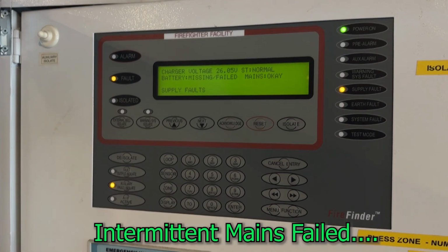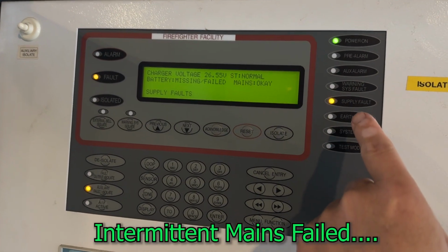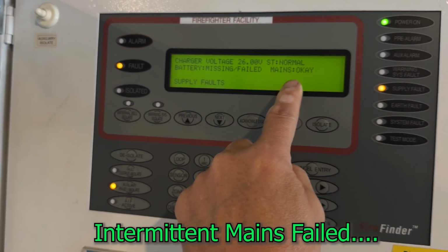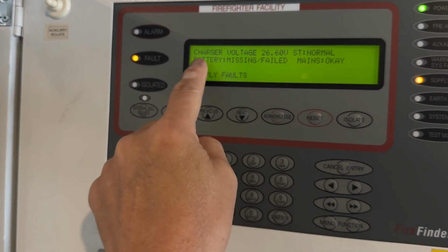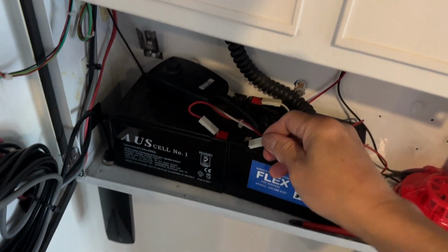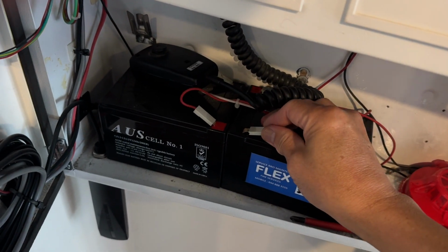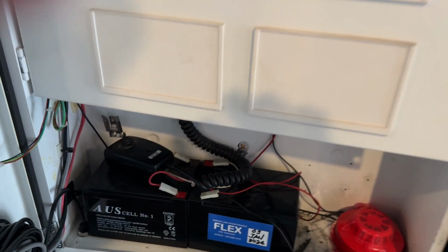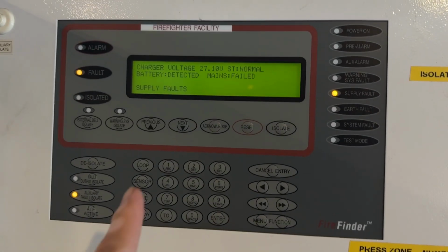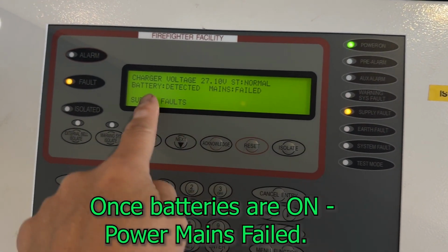Okay, we have that. Power on, supply fault. Says mains okay, missing, battery missing. Okay, let's introduce the battery. Okay, battery on. Right. Mains failed, battery detected.